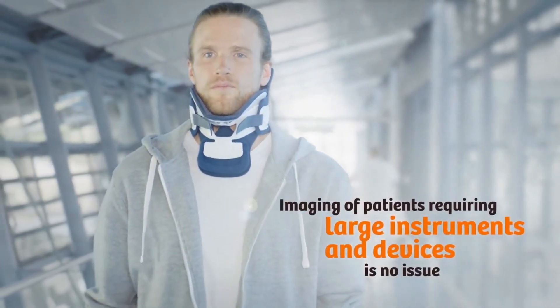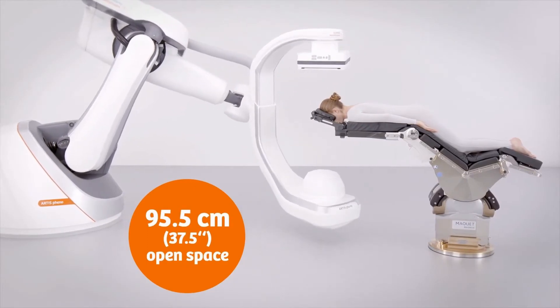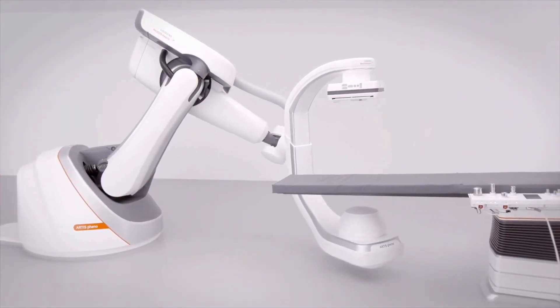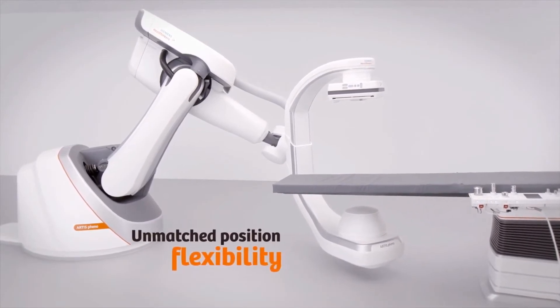Thanks to the unique capabilities of Artis pheno to rotate around complex setups for imaging, Artis pheno offers a wide-space C-arm with a collimator-to-detector distance of 95.5 centimeters, or 37.5 inches — the widest on the market. With a flexible isocenter, Artis pheno provides incredible flexibility for patient positioning, and 2D and 3D imaging are still possible in virtually any patient position you choose.